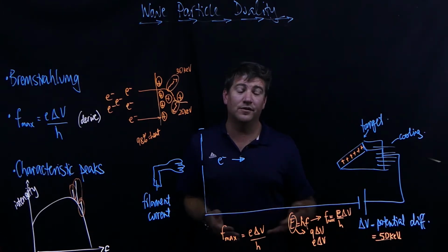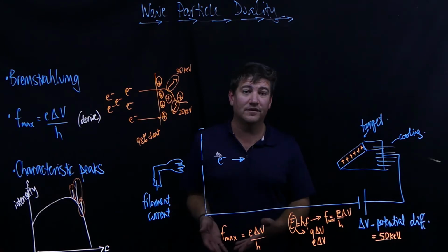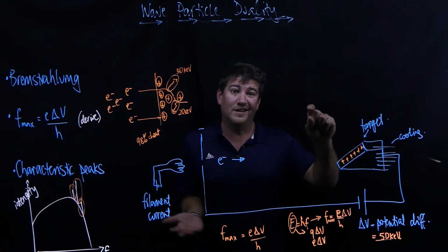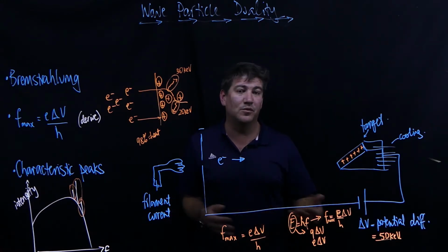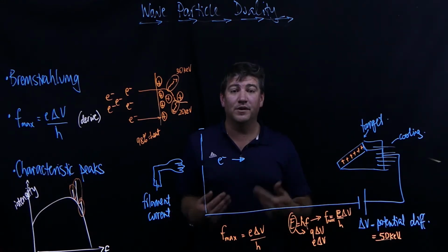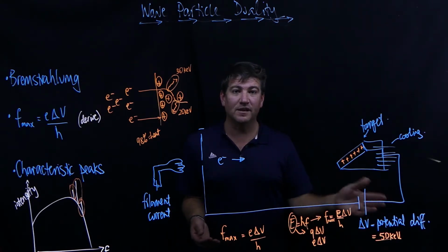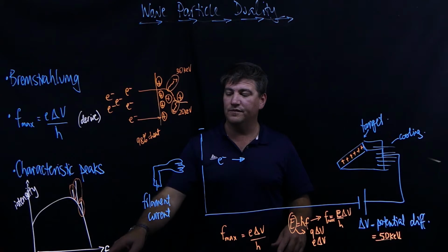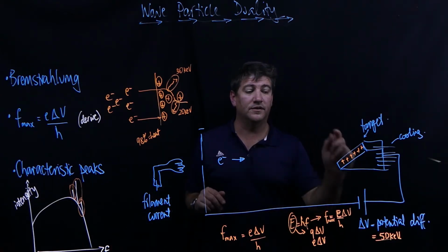If it's something like scanning food products, like a thin layer of chicken breast to see if the bone's been taken out, or fish or something like that, you might use aluminium or magnesium. For the human body, you might use something like tungsten, which can generate X-rays that have a little bit more in terms of the maximum frequency. So we can change the target material.